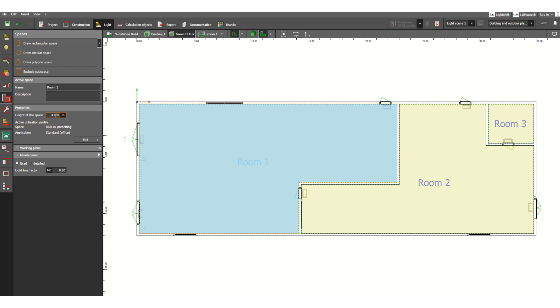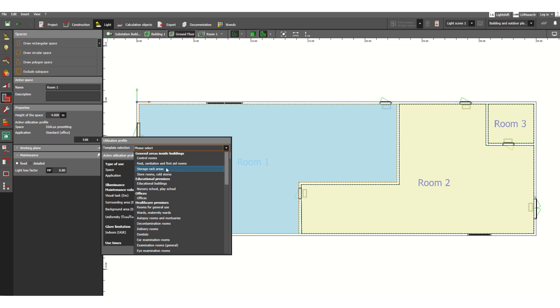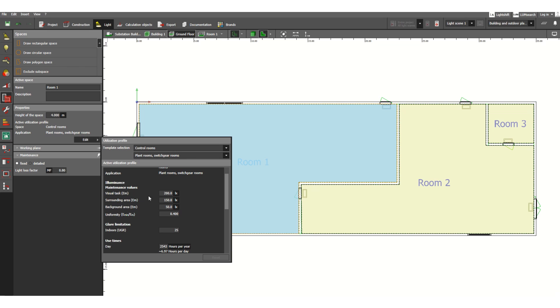Click here and it will show the height of the space — 4 meters, as we defined in our first video with a clear space height of 4 meters. Click Edit. Under template selection, scroll down to choose the room type — for example, control room is 200 lux, or switchgear rooms. The Em value is 200 lux average lux level. You can customize all these values based on your project specification.